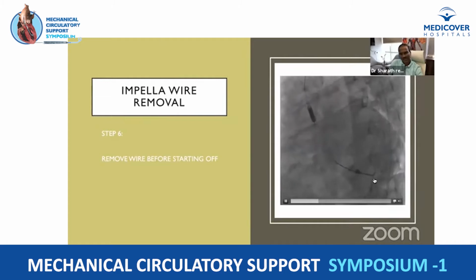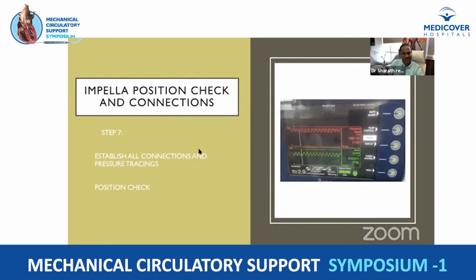Once it has entered the LV, the next important step before you start is removal of the wire. You can see here, this is the 018 wire. This wire comes out of the outflow. So if you start the Impella without removing this wire, you will end up damaging the Impella and it may lead to device malfunction. Make sure you remove the 018 wire and then check your position and also check your connection.